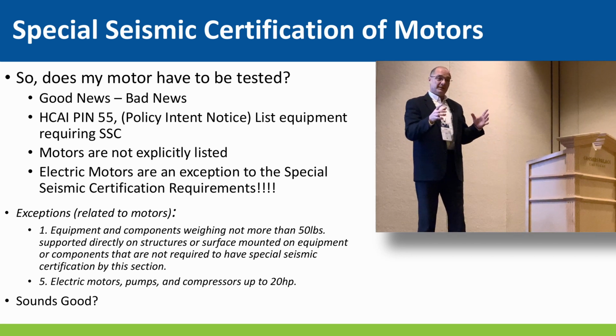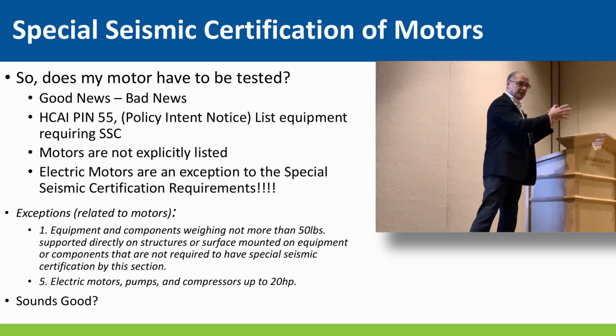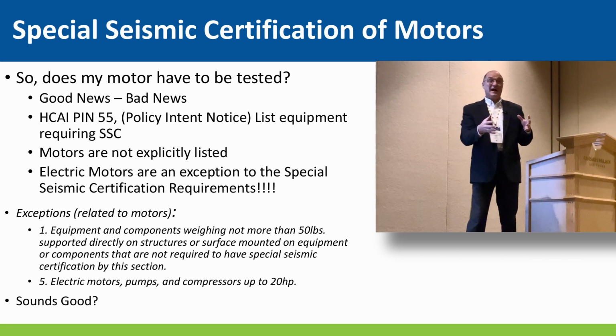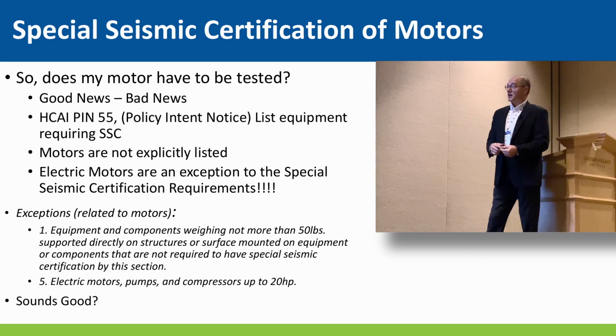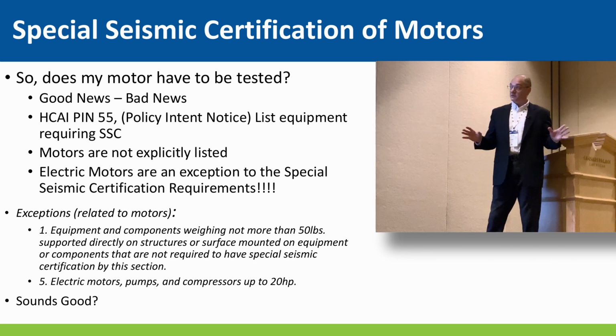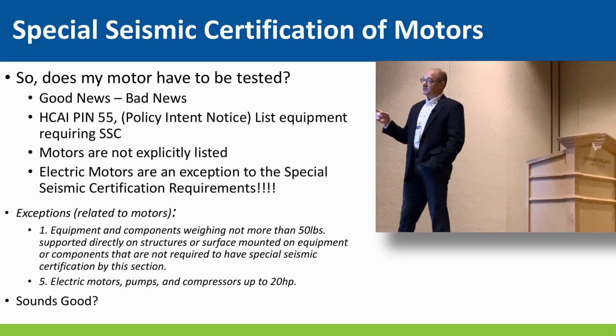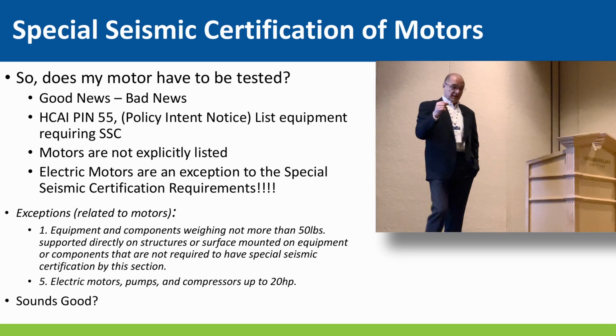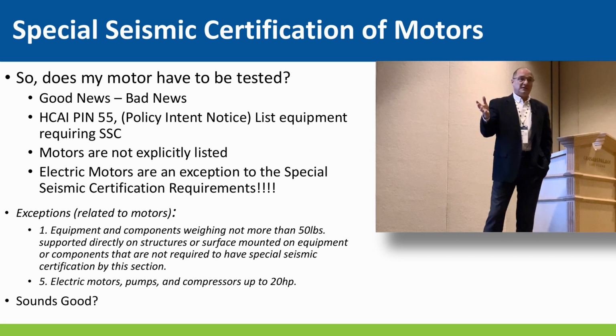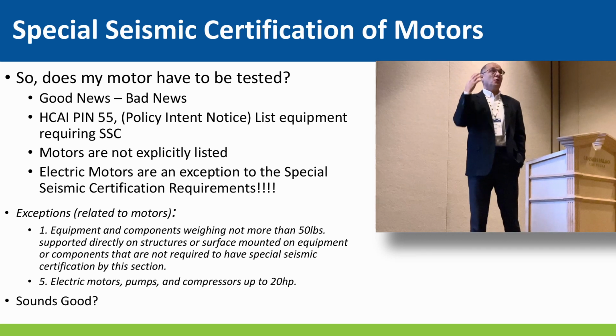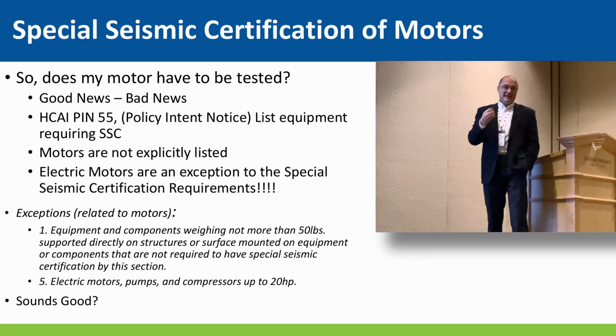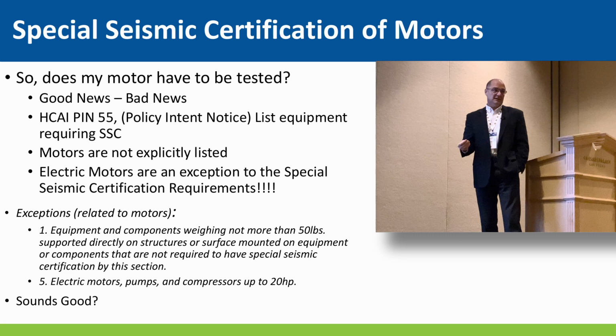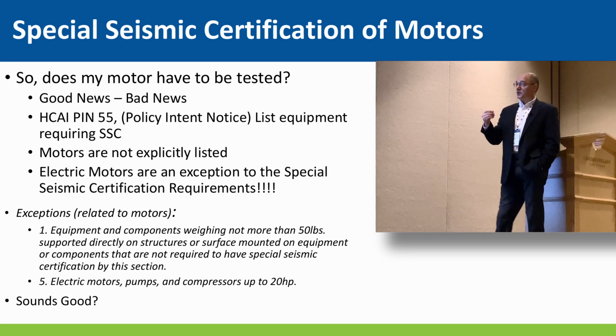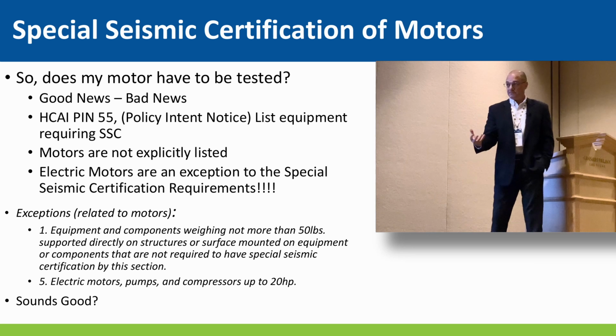Your motor is exempt if you take your motor and bolt it to building structure. How often do you do that? Not very. Your motor is not bolted to building structure, or it's a component that's not required to have special seismic certification—that's a given, if you're 1.0 you don't have to do it. But 'supported directly on structures' basically says your motor can't be exempt, because unless it's a garage door opener, you're bolting it to structure. Your motor is a component in a bigger piece of equipment. It's not bolted to structure, it's only bolted to another component.